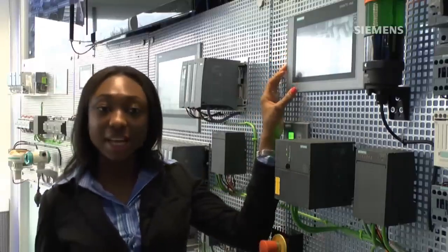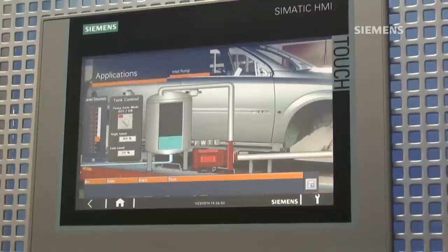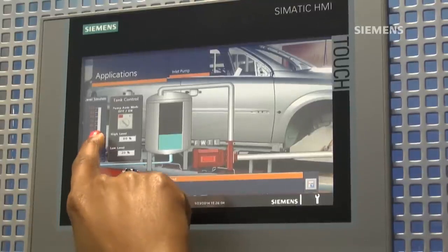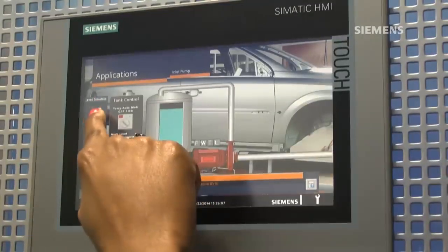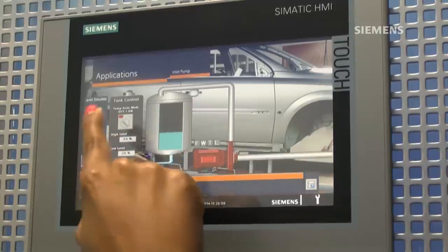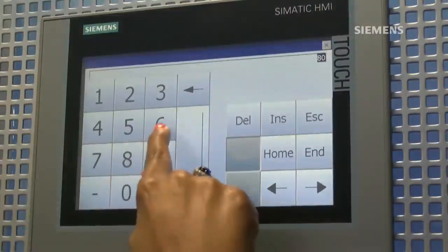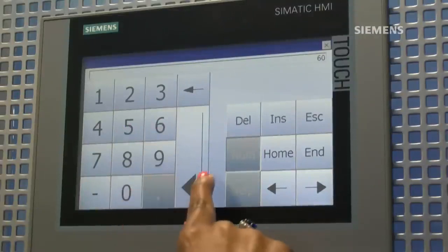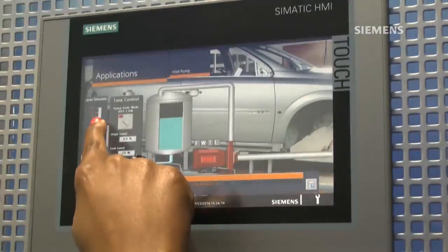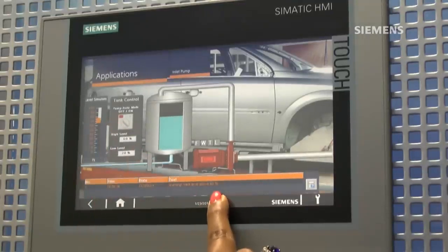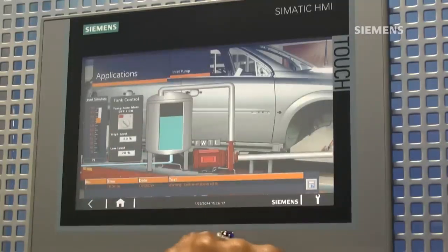In this example, we have a tank in a plant with high and low limits configured. Currently, the high level is 80%. When the tank level goes above this, an alarm is triggered with the limit value embedded in the text. The limit value can also be changed in runtime. This changes when the alarm is triggered and the new value is now shown in the alarm text.